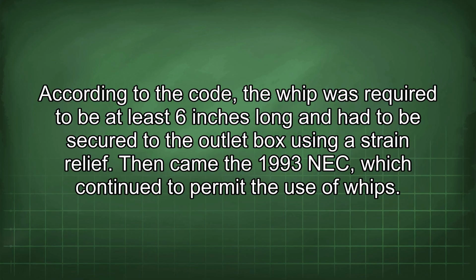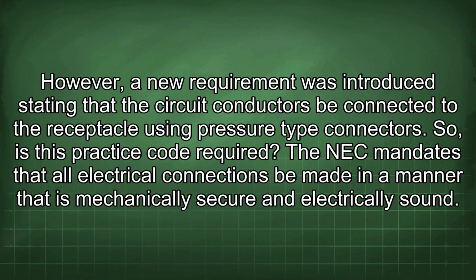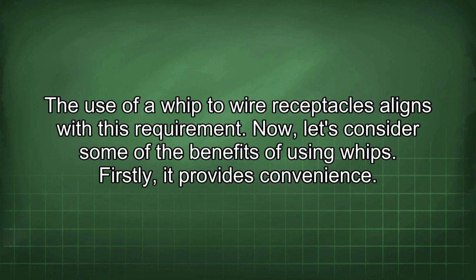Then came the 1993 NEC, which continued to permit the use of whips. However, a new requirement was introduced stating that the circuit conductors be connected to the receptacle using pressure-type connectors. So, is this practice code required? The NEC mandates that all electrical connections be made in a manner that is mechanically secure and electrically sound. The use of a whip to wire receptacles aligns with this requirement.